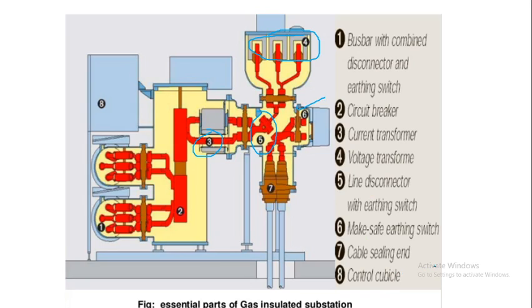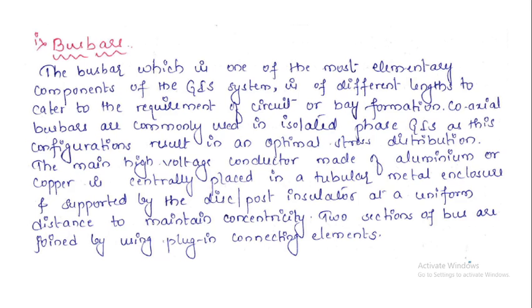The seventh one is cable sealing. This is the seventh equipment, cable sealing, as you can see here. And finally we have the control device or control panel. In this we have two different sections, a local control panel as well as a remote control panel. So these are the different components used in gas insulated substations: bus bar, circuit breaker, current transformer, voltage transformer, line disconnector with earthing switch, make safe earthing switch, cable sealing, as well as the control devices or control cubicles. Next we'll go one by one through these different components and what they are for. First we'll discuss the bus bars.